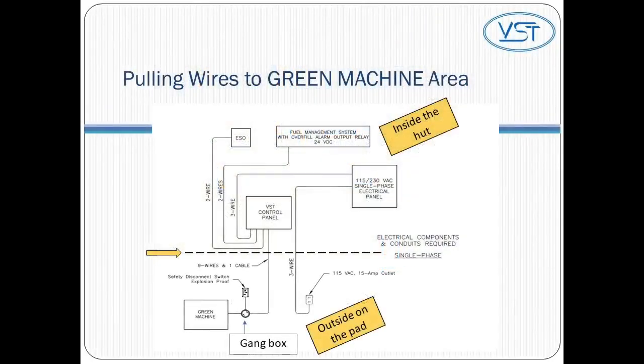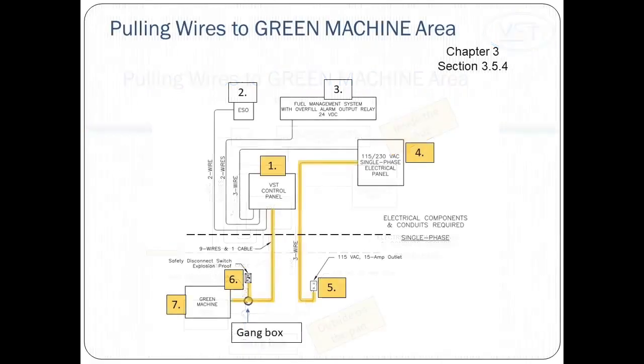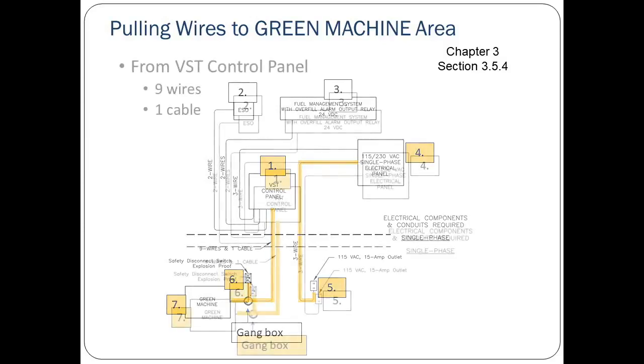Now that you've got the wiring correct for powering the VST control panel, let's look at pulling wires from inside the GDF data hut out to the green machine. Follow along in section 3.5.4 of the manual. Recall that in our earlier graphic, the dotted line represents the wall of the data hut. Any wires passing through this dotted line are to be pulled from inside the hut out to the green machine. A total of 9 wires and 1 cable must be pulled. These wires and cable must be pulled through rigid conduit.